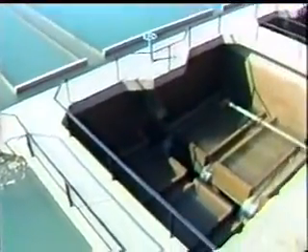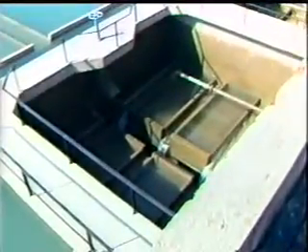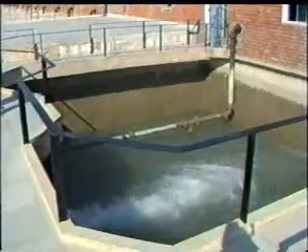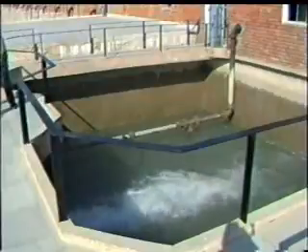The process of backwashing should be continued till all the impurities flow out, which can be judged from the crystal clear water coming up through the filter beds. Different controls are provided for backwashing and controlling the outflow. After backwashing, the filter unit is again ready for use.